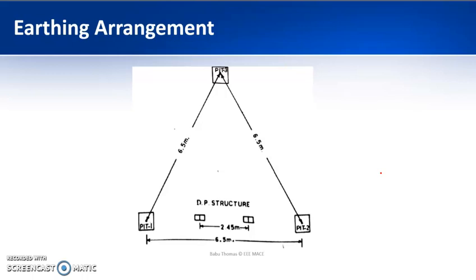Now your outdoor substation has to be earthed. So you are having a double pole structure, and the double pole structure is shown over here. This is the double pole structure, and 3 earth pits are required, pit number 1, 2 and 3. So there are 2 earth pits on either side of your double pole structure, and one of them should be connected to the lightning arrestor, and the other one is to be connected to the neutral of your transformer on the LT side. And the third one is to be connected to the transformer body, to the handle of your gang operated switch, and to the body of the LT switches. And there will also be an interconnection between the 3 pits in the case of an outdoor substation. So that is all about our outdoor substation.